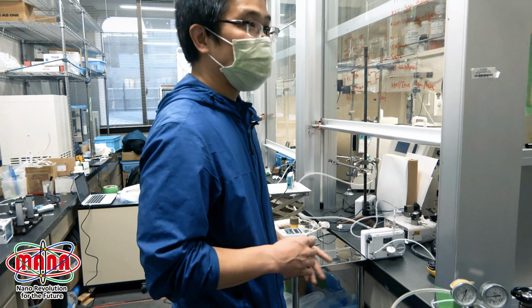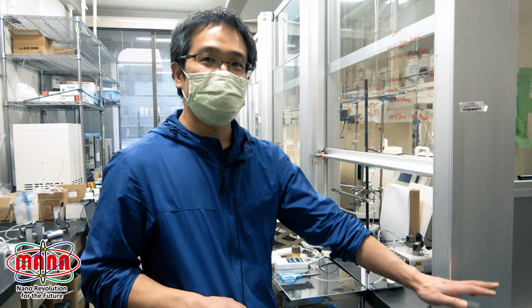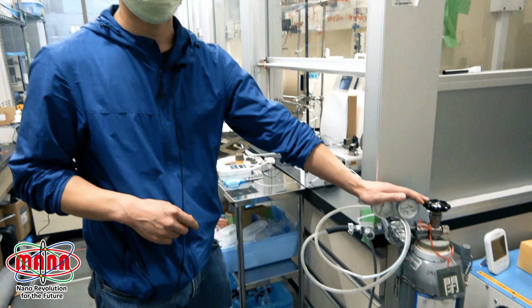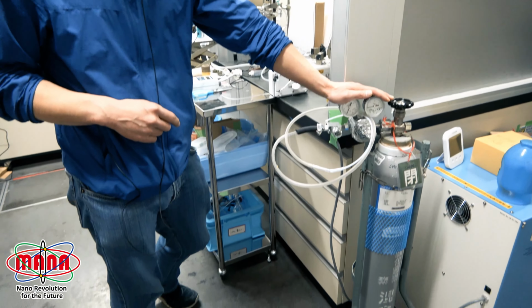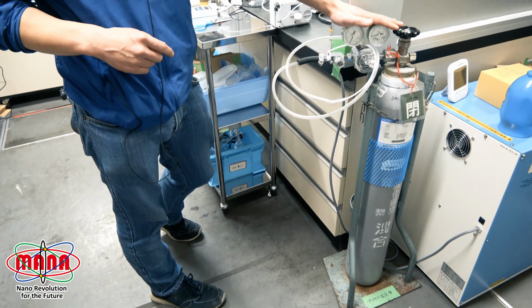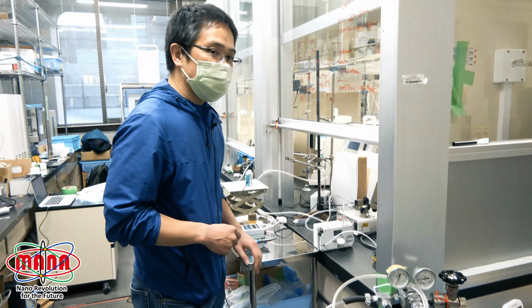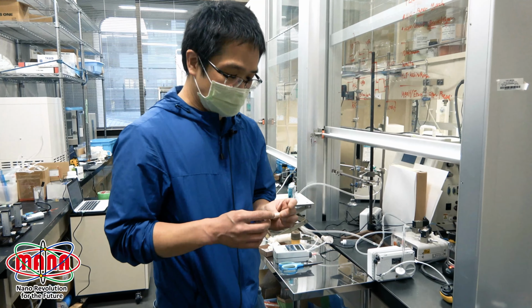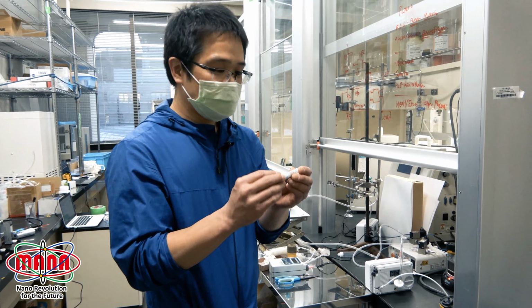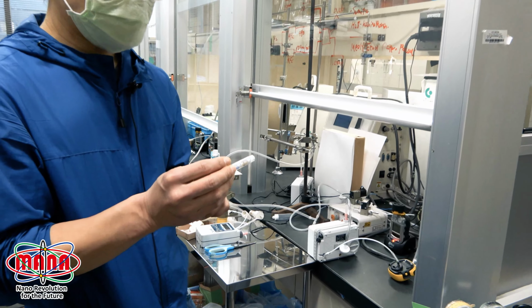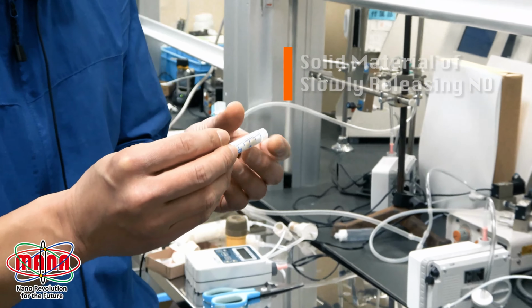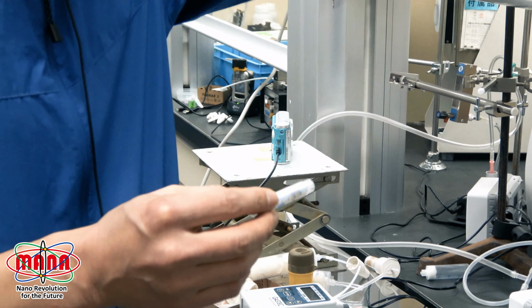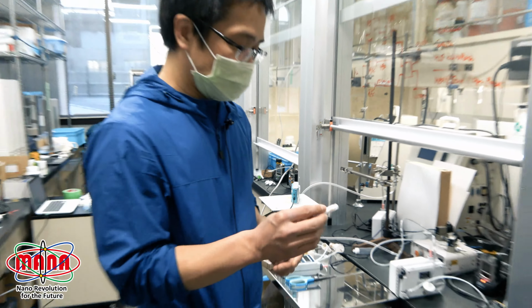However, currently nitric oxide is delivered by this kind of high-pressure gas tank that is very heavy and sometimes dangerous in operation. So in order to solve this problem, we have developed this kind of solid material that generates a medically useful quantity of nitric oxide in response to humidity in air.